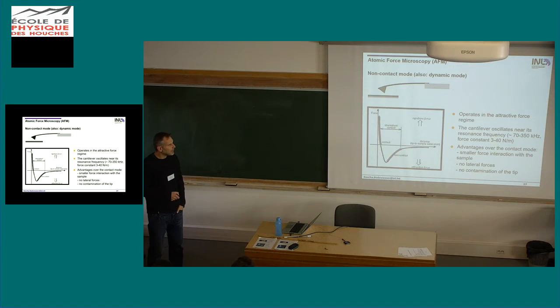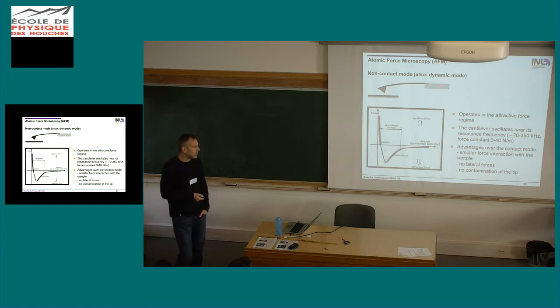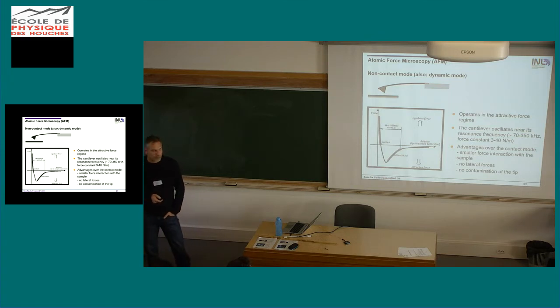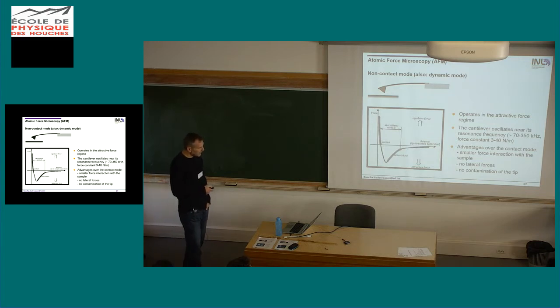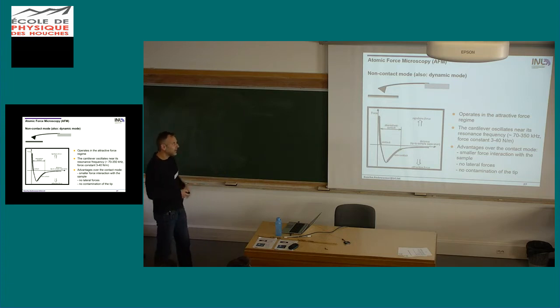resonance frequency. We typically use stiffer cantilevers, so they are not as soft as the ones in contact mode. And the resonance frequency is somewhere from, let's say, 100 kilohertz to 1 megahertz, depending on what kind of cantilever you use. So this tip oscillates at this frequency. The advantage of this mode is that since you're not touching your surface at all, you have a much smaller force interaction. You're measuring in the non-contact part here, in the van der Waals interaction.